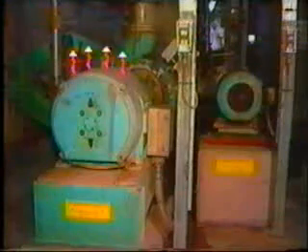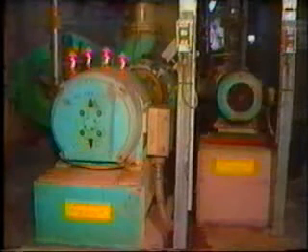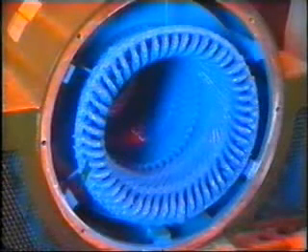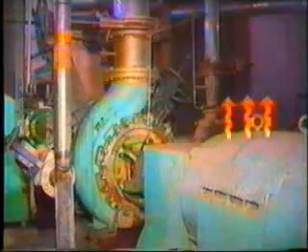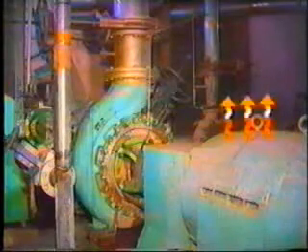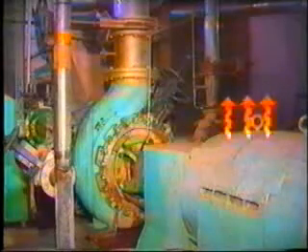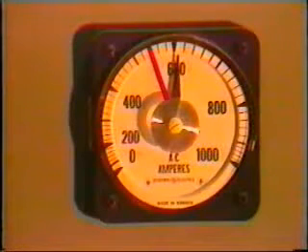A more common problem of the motor is overheating, which may go unnoticed over a period of time. Overheating leads to deterioration and eventual failure of the insulation. This causes a short circuit between phases and to ground. Overheating may be caused by a variety of reasons. The obvious condition that comes to mind is that of overload, where the driven machine, say a fan or pump, is working above the motor's rated capacity. As we have already learned, this leads to considerable increase in current flow through the stator, which causes overheating if the condition is allowed to persist.